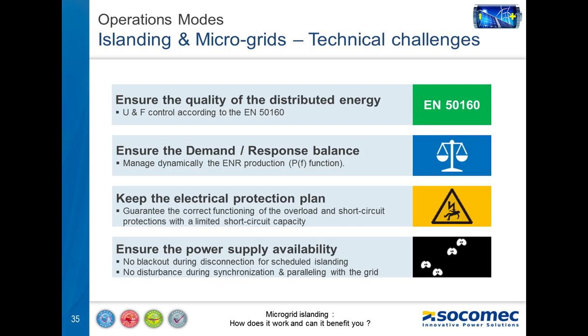Now, let's have a look at the main technical challenges of this kind of project. The first one, like we said previously, is clearly to ensure the quality of the distributed energy and to be compliant with the European standard EN 50160. The second one is to ensure the balance between the demand and the response of the microgrid, taking into consideration the power capacity of the PCS, the energy storage inside the battery, but also the possibility to control the PV production through the PEF function.